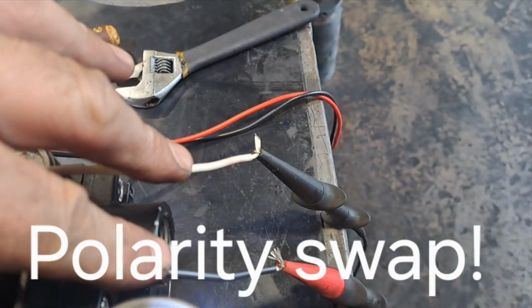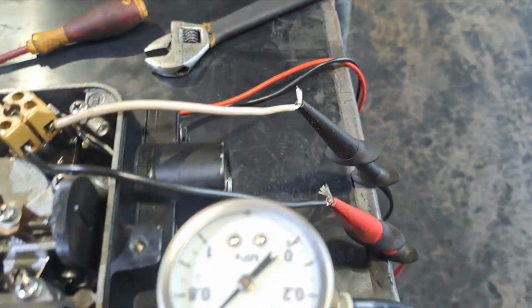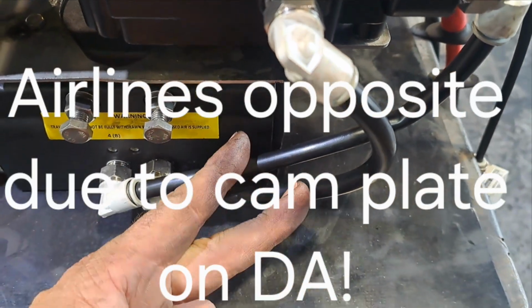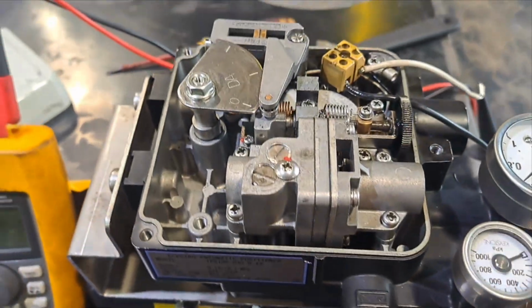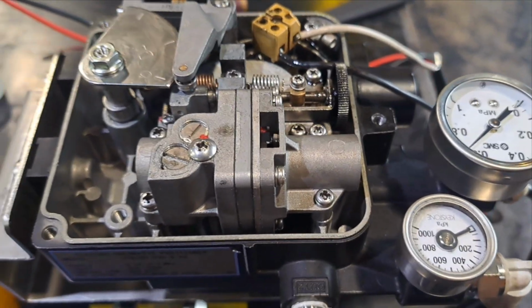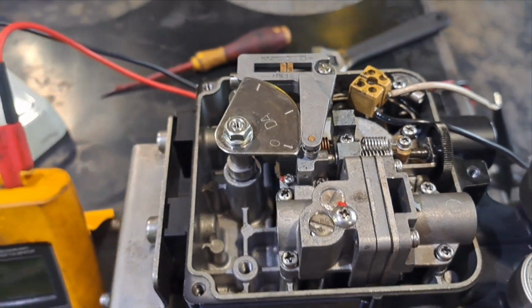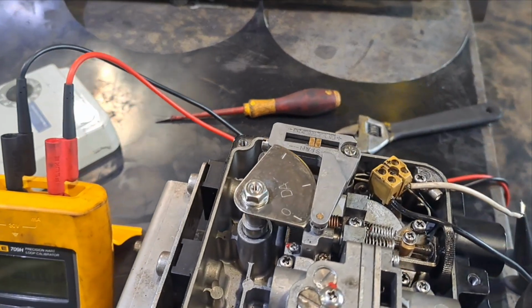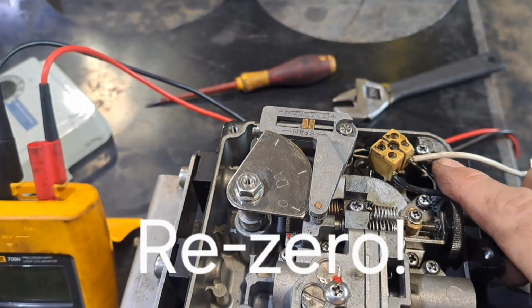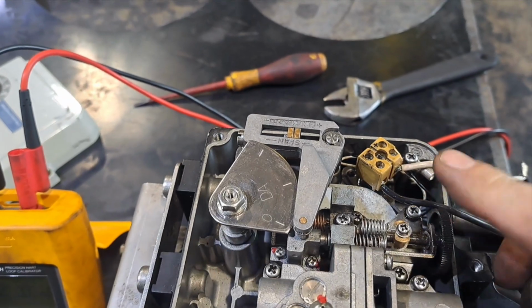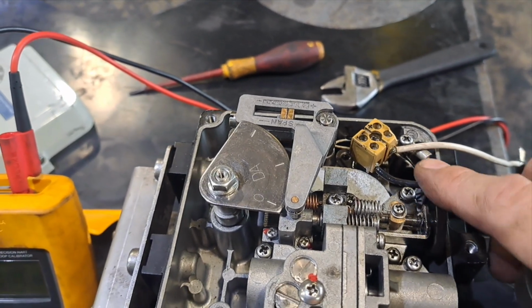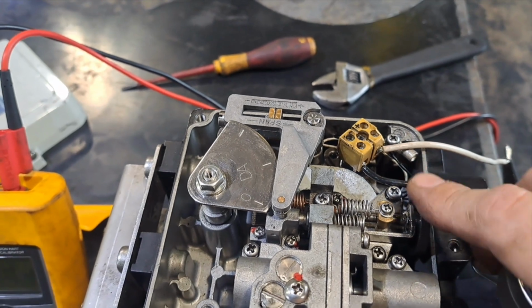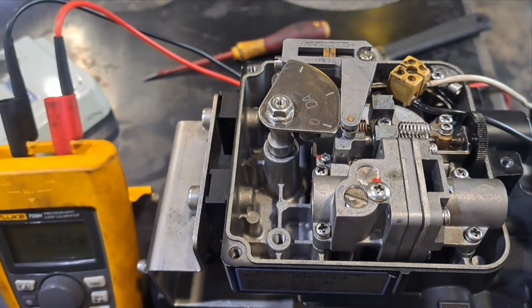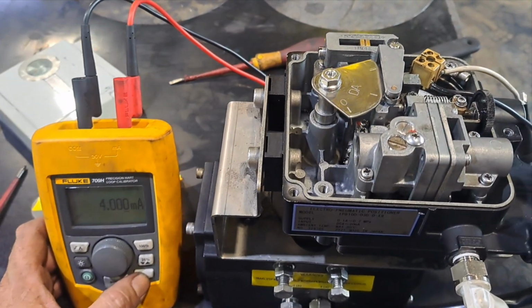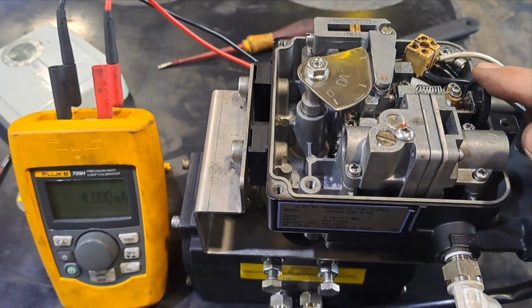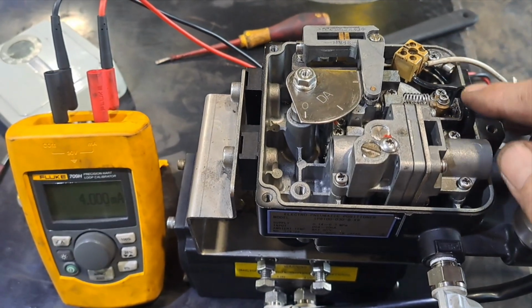The reason why we swap polarity on this setup is so that we can have the 20 milliamp give us the closed signal and the 4 milliamps give us the open signal. So you can imagine if you're going to 0 milliamps with your fault, where you've lost power or the cable got cut, because the 0 milliamp is past the 4 milliamps and 4 milliamps is open, well, we are going to sit in the open position as a fail-safe. Sometimes with setup changes, it helps to go to a different milliamp, like 20 milliamps, just to see which way it goes, to see which way you need to re-zero your position.